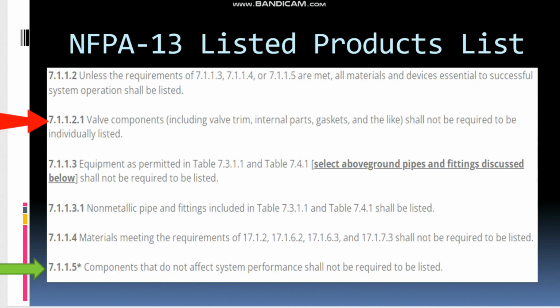NFPA 13, as mentioned here, says valve components shall not be required to be individually listed. A valve has internal parts like the gasket, and all these components need not be listed separately. But the valve as a final end product, like a single component, should be listed. And equipment as permitted in Table 7.3.1, that means if you go to this table, you can see lots of pipe materials. If it is already there in the NFPA, then there is no special need for it to be separately listed. But if it is not there in the table, then there is a requirement that it has to be listed.